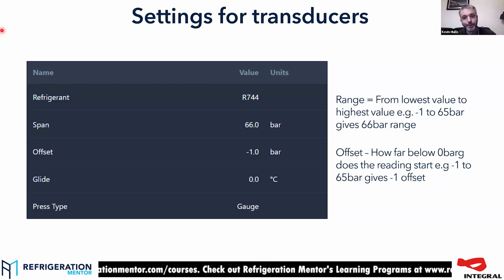It's from the minimum to the maximum, and then you use the offset to tell it whether it starts below 0 or not. Now, if you've got a -1 transducer, it starts below 0, so you have to tell it it's a -1 offset. Cannot tell you how often I see this set incorrectly. If you've got a Carel transducer, for example, in 4 to 20 milliamp, very often they start at 0. So you might have a 0 to 60 bar transducer, span 60, offset 0.